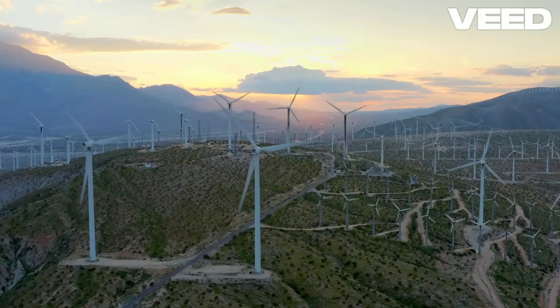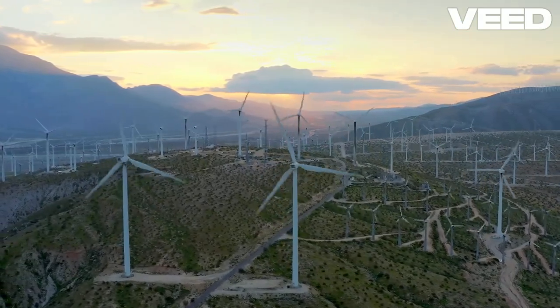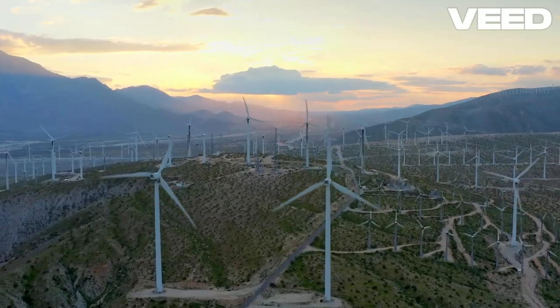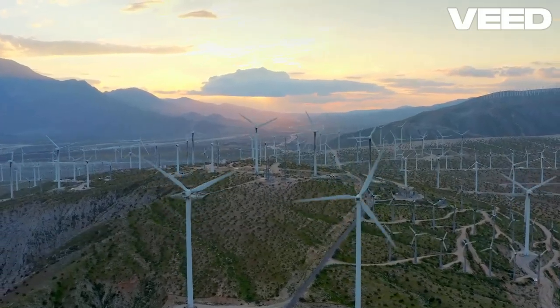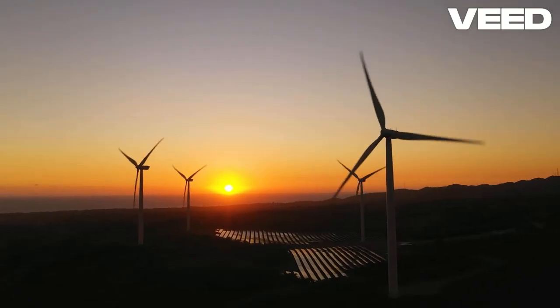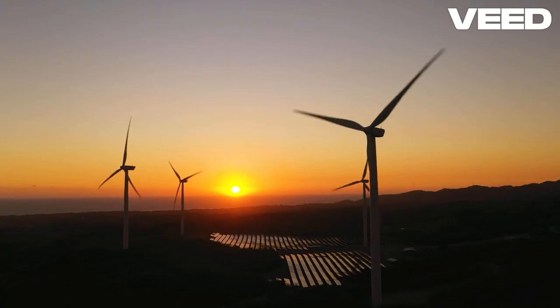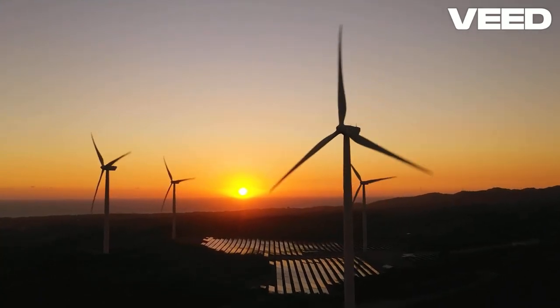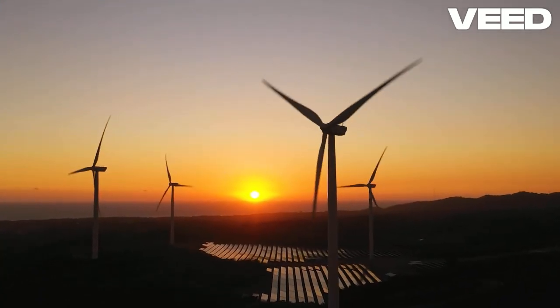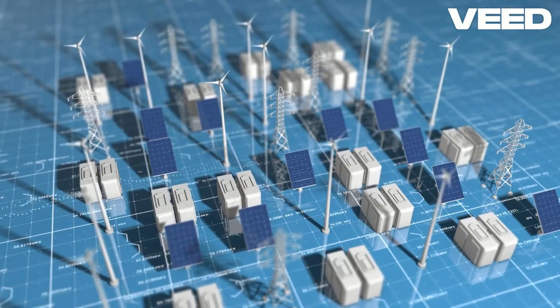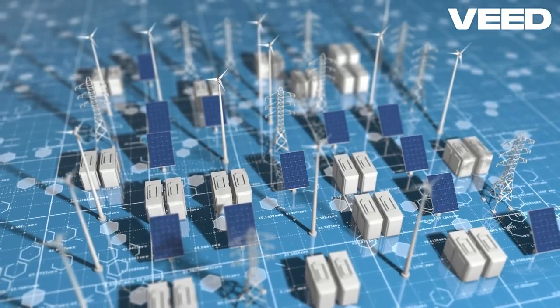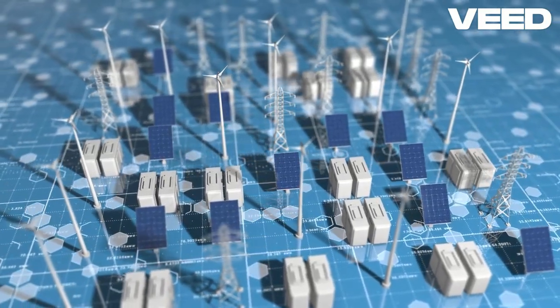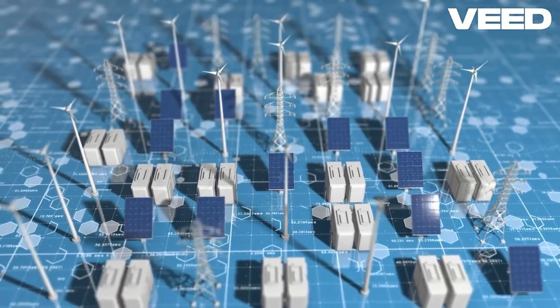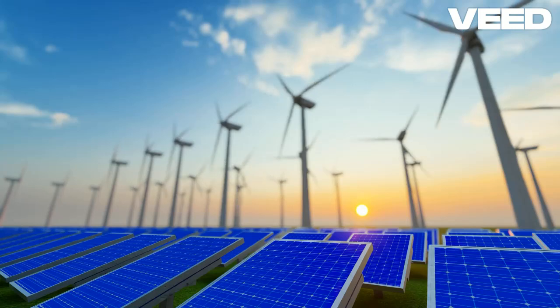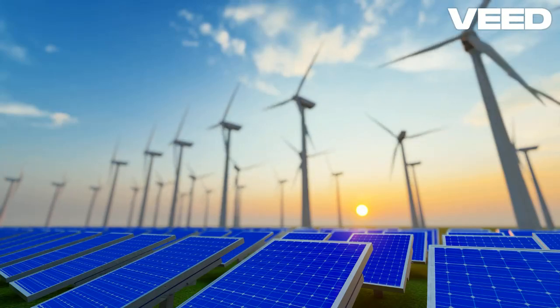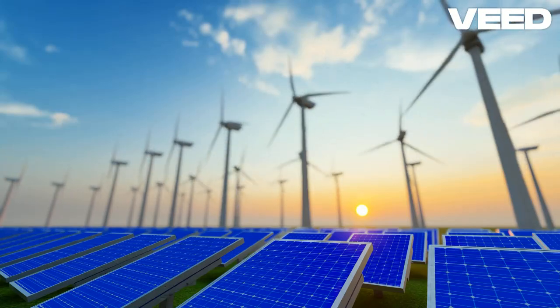To counteract this, we use frequency regulation techniques. The first layer is primary regulation, where generators respond almost immediately to frequency changes by adjusting their output. Secondary regulation, often managed by automatic generation control (AGC), kicks in next, rebalancing the system over several minutes. Finally, tertiary regulation involves redispatching resources to optimize overall grid performance. Yet, these traditional mechanisms are not enough in a grid dominated by renewables.